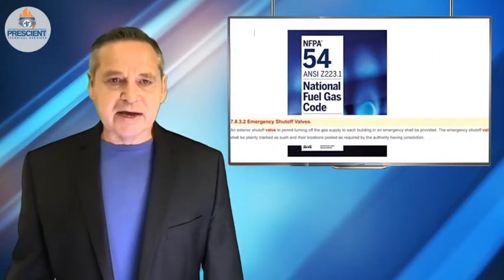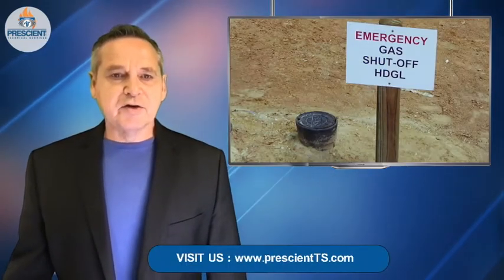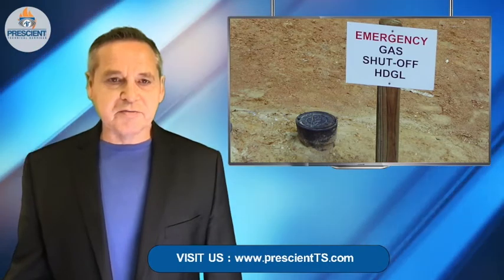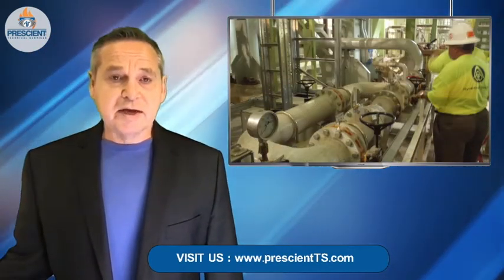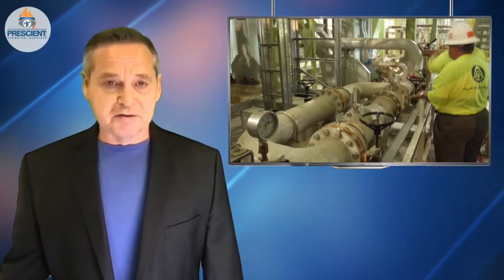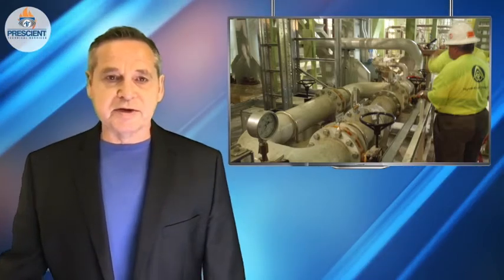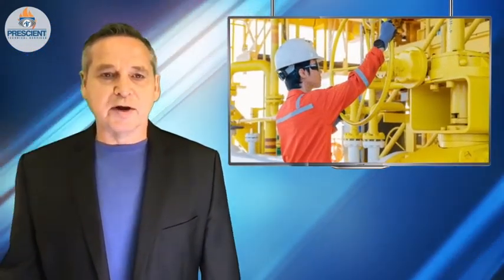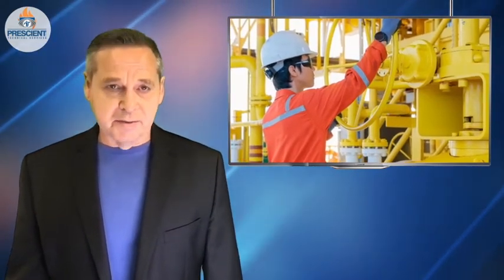You have to follow that gas line inside the facility. NFPA 54 also says there should be a manual isolation valve somewhere outside of a building. If you have manual isolation valves associated with the mains and the distribution systems inside or outside a building, are they accessible, or are they 20 feet in the air? Are there chain operators or gear operators that haven't been serviced and frankly don't work? Now is the time to find out about those things, not when you really need them.